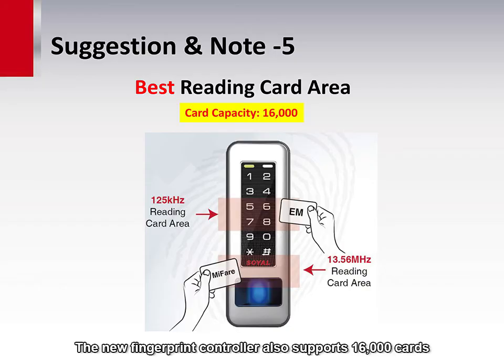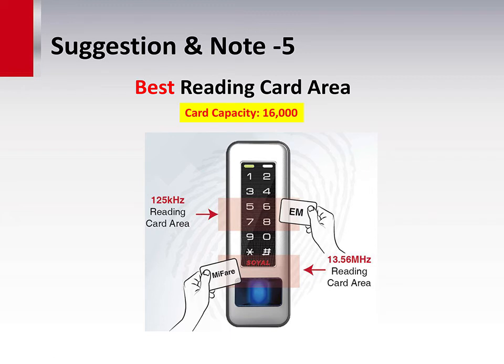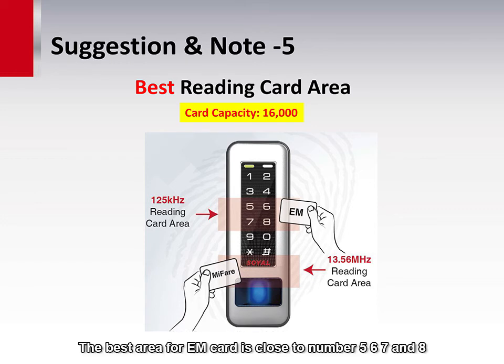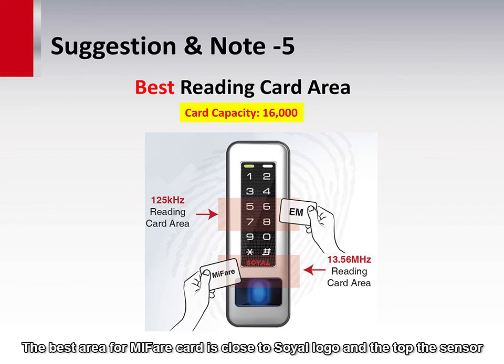The new fingerprint controller also supports 16,000 cards, but the card reading area is different for the two kinds of frequency cards. Please follow the suggestion to respectively read EM and Mifare cards around the correct area. The best area for an EM card is close to numbers 5, 6, 7, and 8. The best area for a Mifare card is close to the Soyal logo and the top of the sensor.